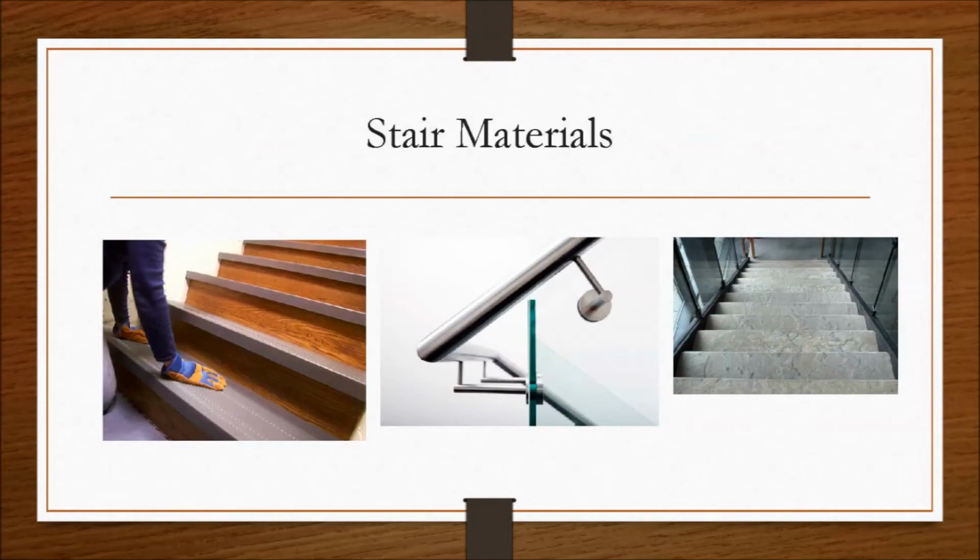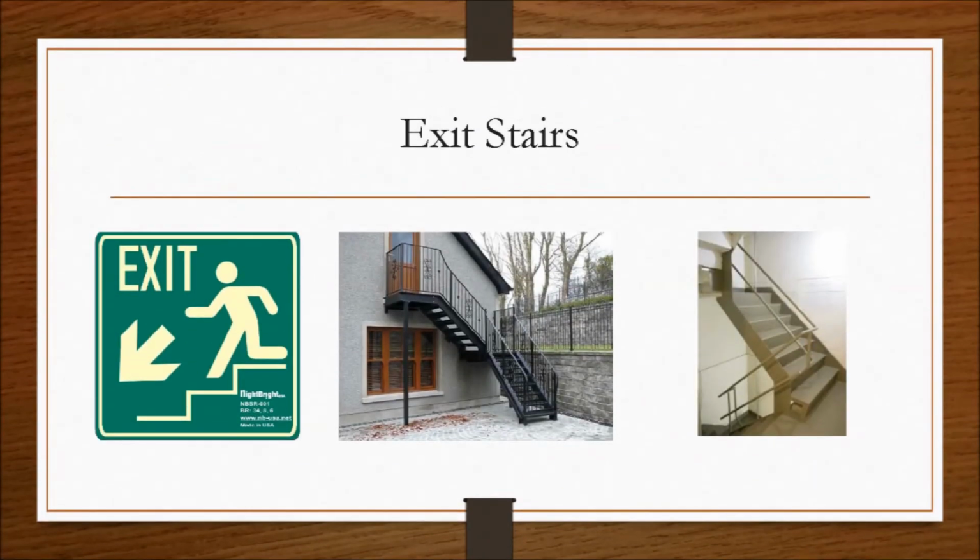The greatest danger to building occupants in a fire is not flame, but the smoke. When an exit stairway is enclosed by walls of fire-rated construction and is accessible by a vestibule or open exterior balcony, the stairway is a smoke-proof enclosure. This air is kept under positive air pressure so that smoke will not tend to enter.